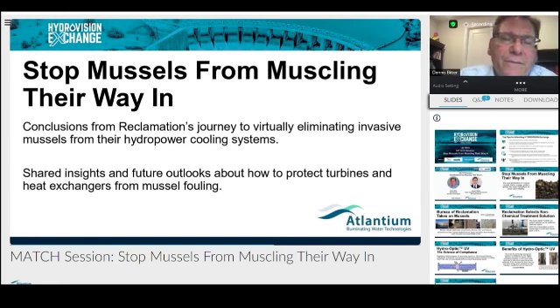That's a good point, I'd like to add to that. The Hydro-Optic UV is similar to Legos - it's easily expandable at a future date. You can start off controlling mussels, as they did down at Parker Dam. But as the slime and colonial hydroids arrived, they still had some capacity to increase the energy and take care of the colonial hydroids, the slime essentially. In cases where more complex organisms may come along, maybe bryozoa, and you need more energy, the Hydro-Optic UV can be expanded to increase that energy.